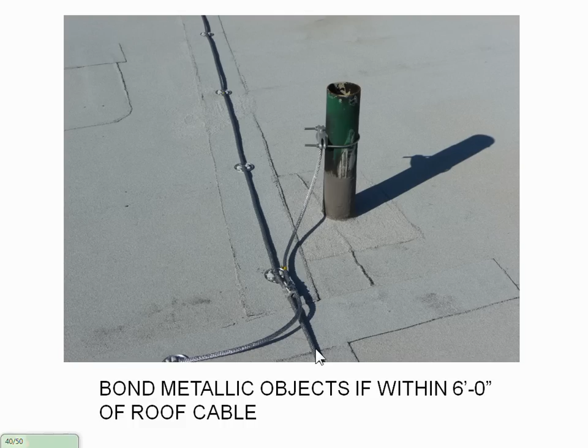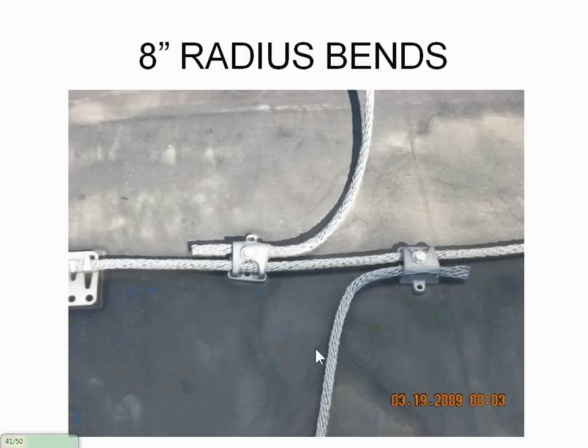This is something we do in the field. Lightning has a hard time turning sharp corners. So what we do is make a gentle 8-inch radius bend. Lightning strikes here and needs an easy path to ground. Lightning travels at extreme speeds. If lightning were to strike here, it doesn't have time to make this sharp turn. It's actually just going to keep shooting off of the cable. So what we do is try to make the bends as easy as possible.